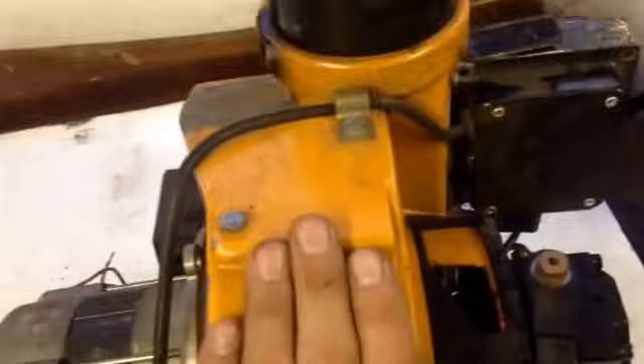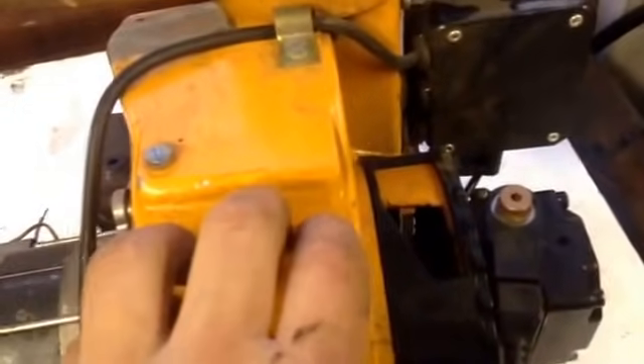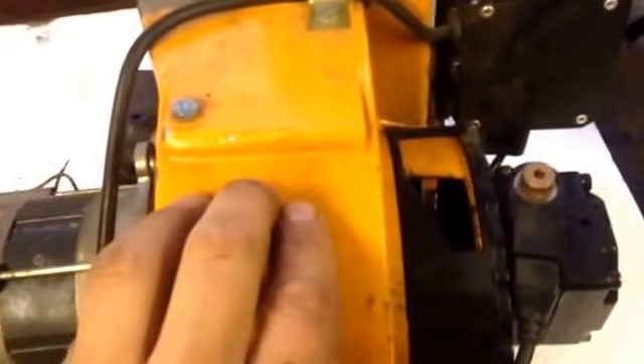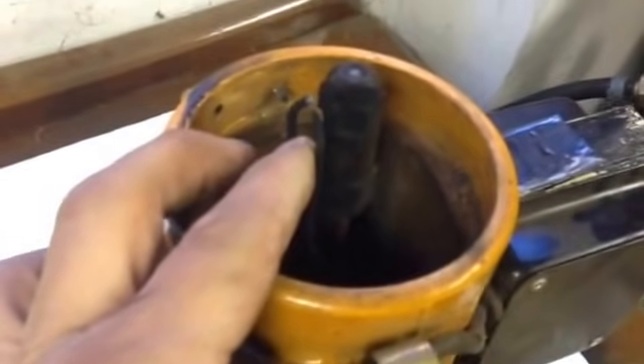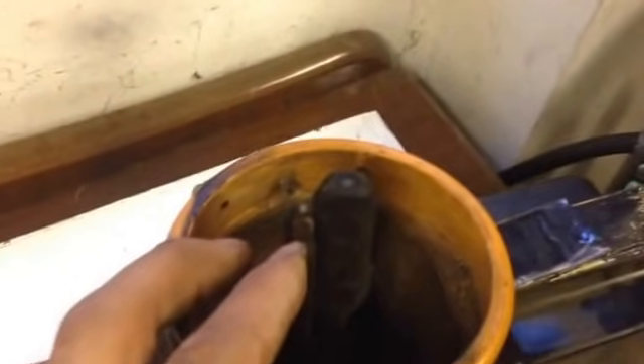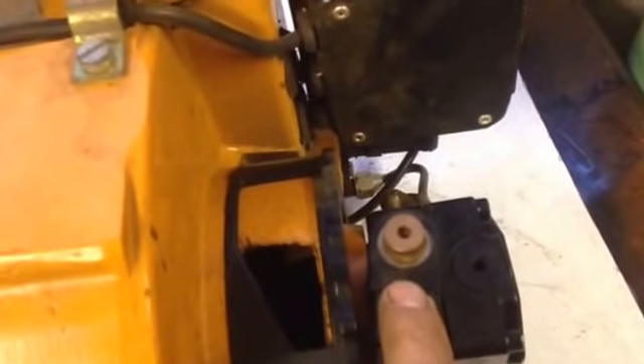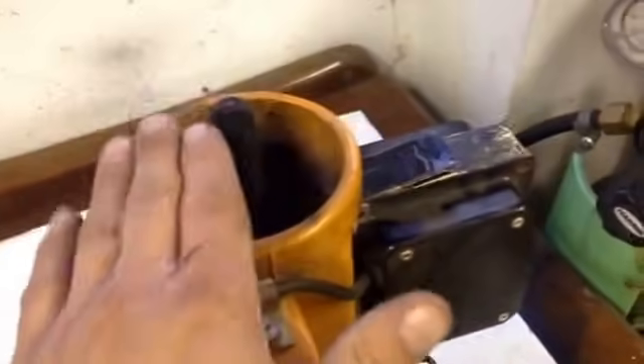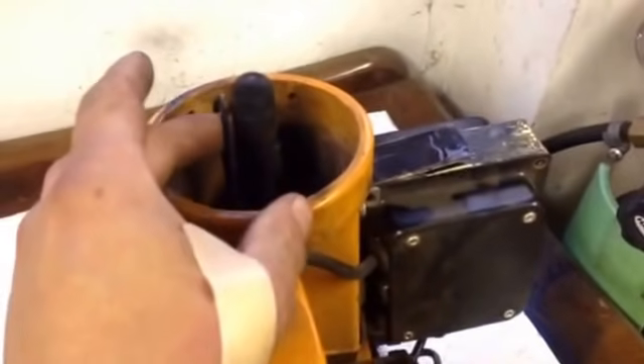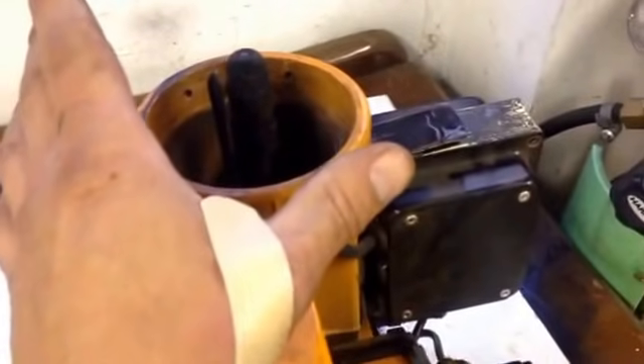The way these work is, first of all, it's going to blow for a minute to clear the chamber - no fuel, no spark, no nothing. You should listen for it blowing. Once it's sent air through the chamber, it will then start producing a spark from the little probes here, and you should be able to hear that. Once it's done that, the solenoid opens to let diesel through, which is then ignited. So you should hear fan, fan and spark, fan, spark and ignition. Once it's done that, you should then hear the ignition stop and the flame continue.